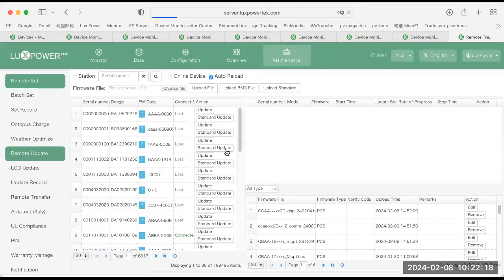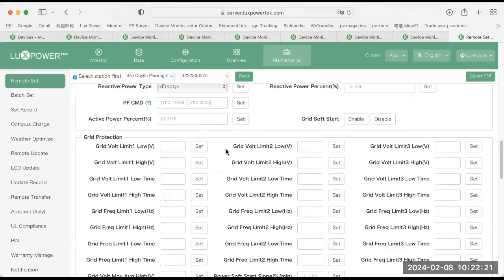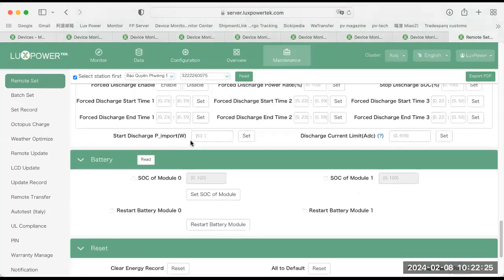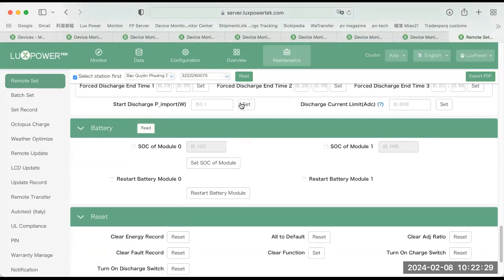And other than remote update, you can also remotely restart the battery here on the remote set page. Where you scroll down to the bottom, you can see a battery section here. You hit the Read button, and then you can restart the battery module. It depends on how many batteries you paralleled here. So in this case, we have 2. But if you have more batteries paralleled, then the page will show you more buttons to see which one you want to restart. So it's very easy for installers to just remotely control all the battery functions we have. A lot of our installers were struggling with other batteries because sometimes the battery over discharged, and then they need to go back to that site again to physically restart the battery so it can be charged up.